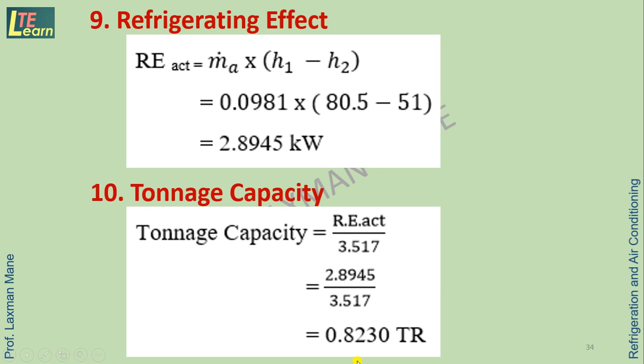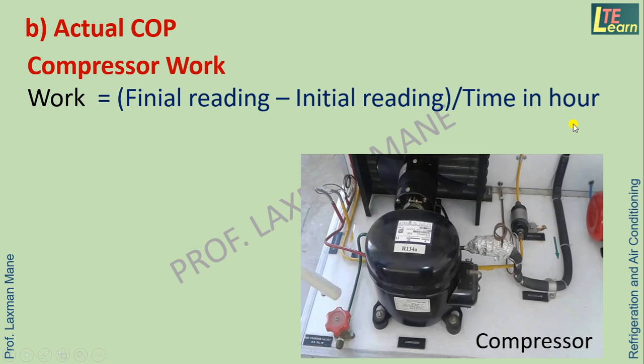Next is actual COP, meaning coefficient of performance of the system. In this, compressor work is to be measured. Here the electrical consumption by the compressor is measured using an energy meter, so we take the initial and final reading of the energy meter. The formula of compressor work is energy meter final reading minus initial reading divided by time of the test. So we take the final and initial readings from the observation table, divided by time in minutes. This we convert into hours. Thus we find the work of the compressor in kilowatt.